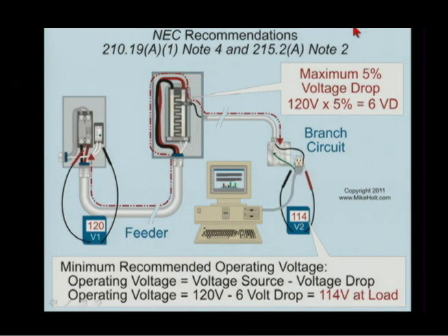And that's if you're at 120 at the source, correct? Because you could vary. Correct me if I'm wrong, Mike. If I took a meter to a service any place and I get 121, I go across the street, I read 119. Well, what we're talking about works really well for exam preparation, but not in reality. Because in reality, it's a little different ball game. In reality, we don't have 120 volts. It could be 116 volts today. It could be 128 volts. And this morning it's higher, or last night it was lower. In other words, it's always a moving target.